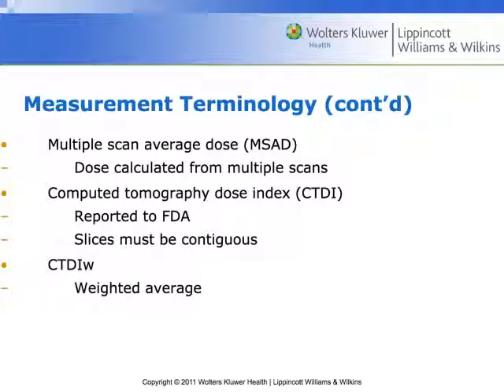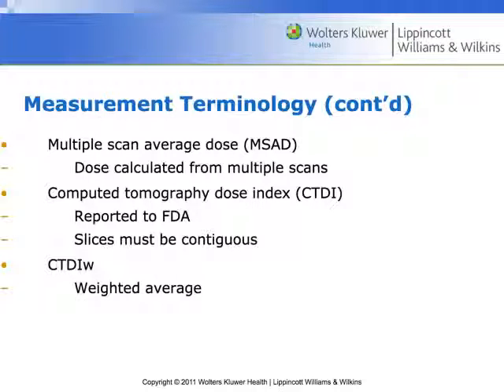This is why we drive toward a CTDI volumetric. Before getting into that, let's talk about the MSAD — the multiple scan average dose. It takes into account the tailing effect along the Z-axis from one slice to another, calculated over a series of multiple scans. When physicists do annual QC, they insert a pencil ion chamber into a uniform phantom, scan it repeatedly, and come up with an MSAD — the volumetric dose resulting from those multiple scans.